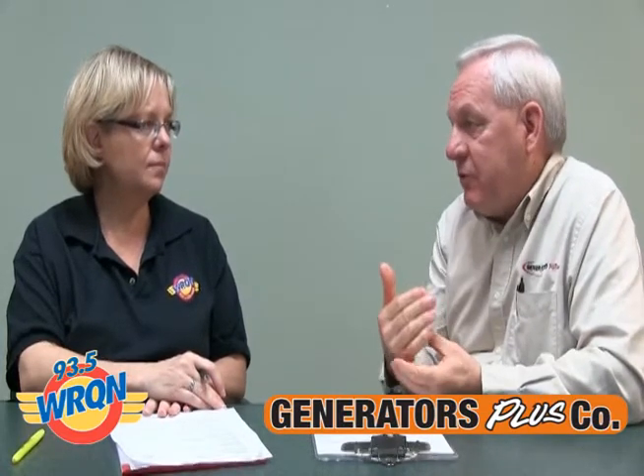And so what happens typically is they call us because the generator won't start or won't run properly. And we'll go out there and we'll find out, well, okay, yes, you used the wrong size gas line. Or we'll have to tell them, you know what, you're too close to an opening in the house for the exhaust. So you have to move that generator to be legal. And this is where we come in, because we know exactly what needs to be done.